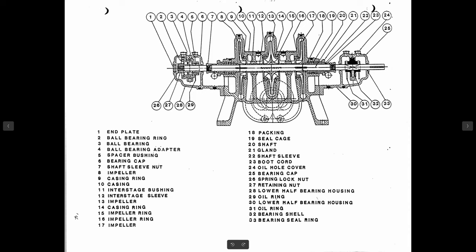This is the first stage impeller here - it's a double suction. The vent line came off the suction side and pumped down here, so the first stage impeller saw the same pressure inside the surface condenser so the water would flow by gravity. The discharge from this fed both second stage impellers on each side. This maintained positive pressure to keep the air out. You had your gland out here with packing. Usually the pump would use the discharge water for feeding in here for the packing. For start it used demin water.